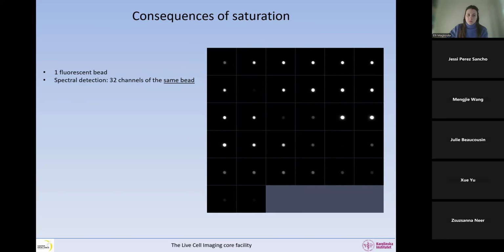When we want to image things simultaneously, we are shining several lasers at the same time on a single-point confocal, and the fluorescence light that comes from the sample is complex because it corresponds to the emission of several fluorophores. Then we split the emission light on a grating or a prism, and we put lots of detectors there.